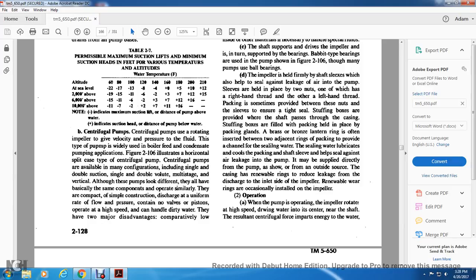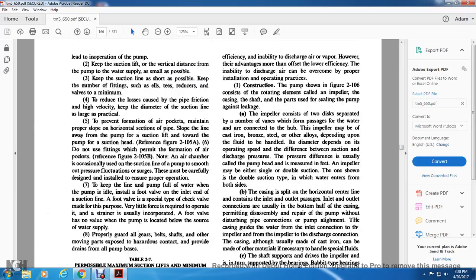The pump operating with a high speed can handle the dirty water. They have two major disadvantages: comparatively low efficiency and inability to discharge air and vapor. However, their advantages more than offset the lower efficiency. The inability to discharge air can be overcome by proper installation and operation practices.